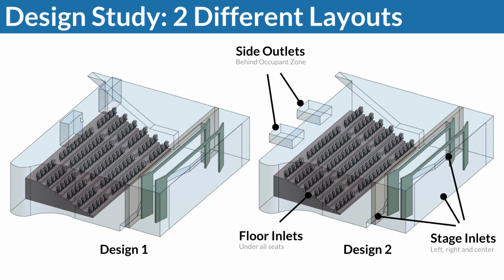On the left, again, we can see the big inlets, and on the right, we can see that these have now been transformed so that the air actually leaves the room here, right? And then we've got the inlets below the occupants, and also the stage, also the inlets, right? So changed approach, same heat, and interestingly enough, also the exact same energy being used, right?